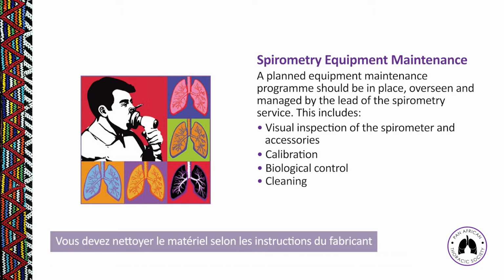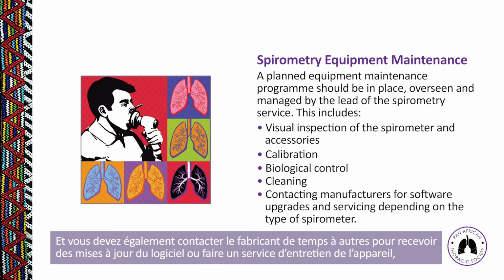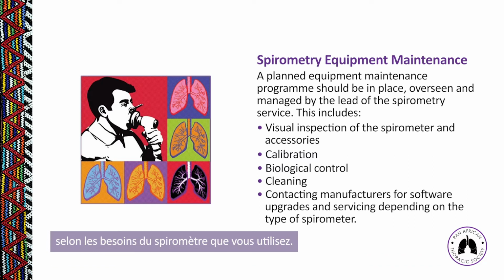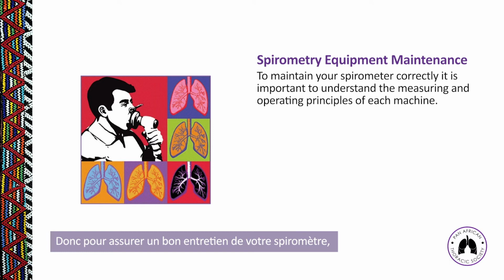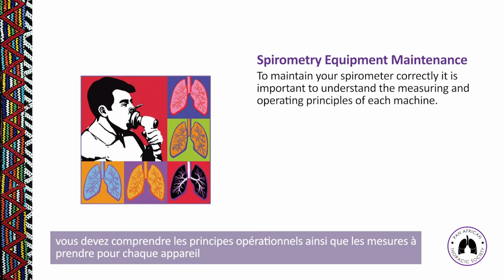You need to clean your equipment according to manufacturer's instructions, and you need to contact the manufacturers periodically for software upgrades and for servicing, depending on the type of spirometer you have. To maintain your spirometer correctly, it is important to understand the measuring and operating principles of each of the devices.